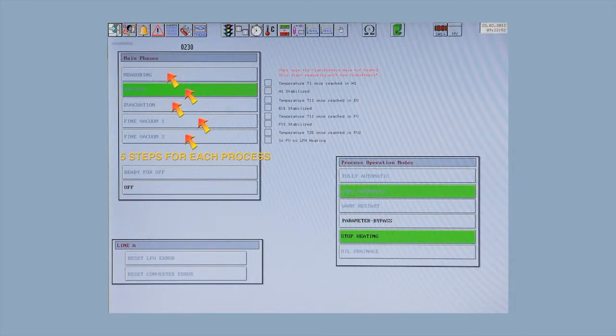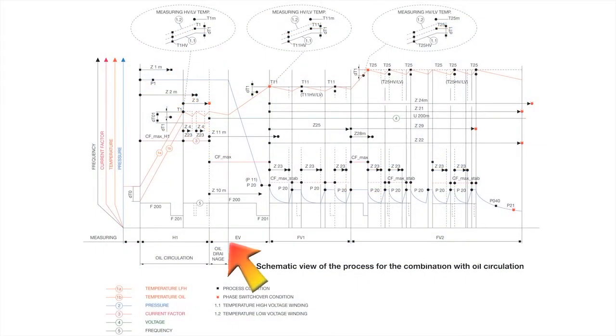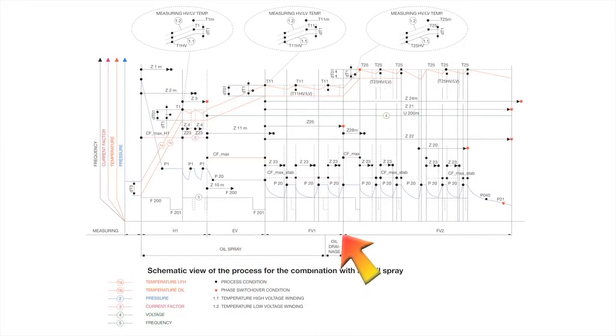Each one of the 2 processes has the same number of key steps. They differ in timing of the oil removal from the transformer. For the oil circulation process, the oil is removed at the beginning of the evaporation step, as shown here. For the oil spray process, it is removed at the end of the fine vacuum 1 step. The first step for a new and cold transformer is the measuring step. This is followed by the main heating step called Heat 1. During the first 2 stages, no vacuum is applied to the transformer. At the evaporation step, the vacuum is applied to the system along with continued heating.